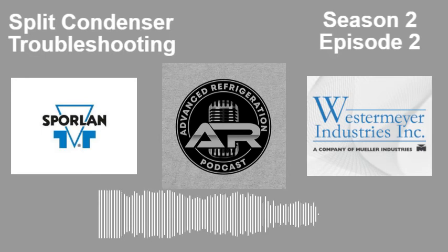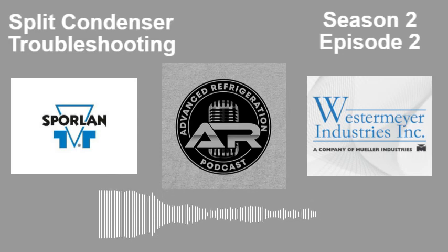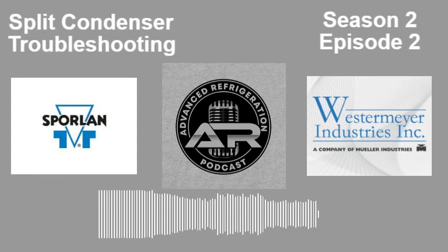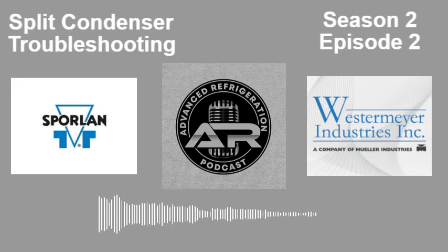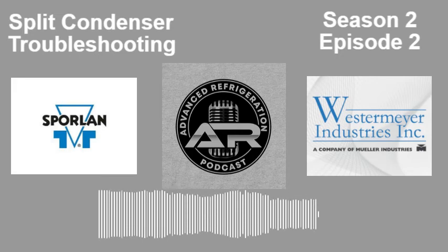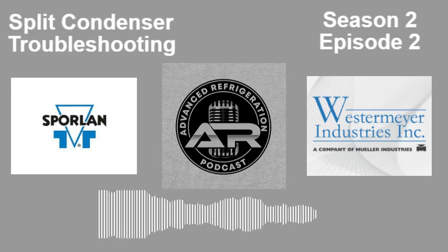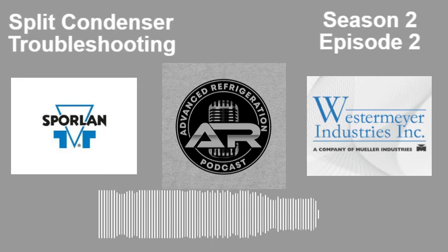With the Walmart and Sam's stuff, generally the rack is not controlling the split stuff, especially if you have a Danfoss drive. The Danfoss drive is controlling it. Some customers split off temperature, like Brett said, like 50 degrees, 40 degrees, something like that. Walmart splits off pressure. They have specific pressure set points for each refrigerant they have and whatever kind of store they have, and they split off pressure. So if you have a smart Danfoss drive, meaning it's controlling the fans, it's actually splitting off of pressure.